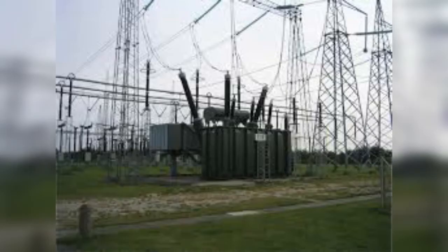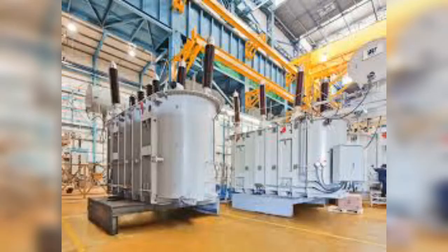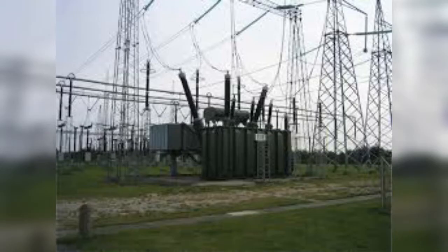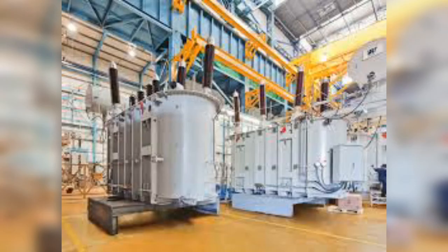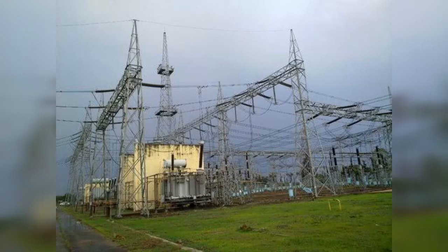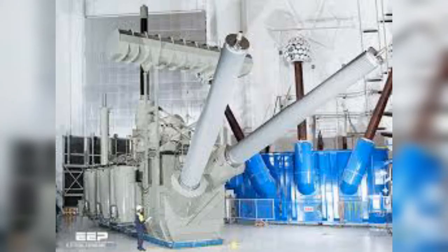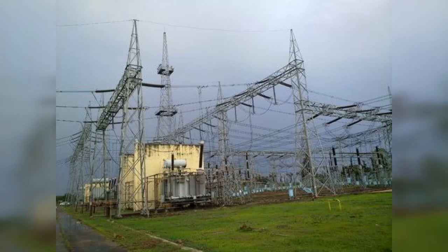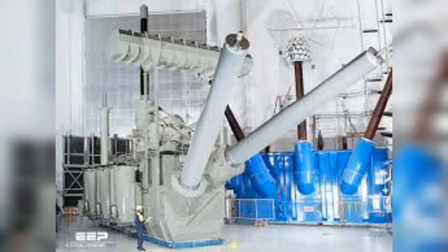The 400 kV substation now needs to be replaced due to its age and due to the upgrade of the active power output capacity of generators. Means these substations depend upon the generation and the national grid position. Some of the substation owners have proposed the two breaker arrangement design for a new substation and asked for opinions on the suggested design.